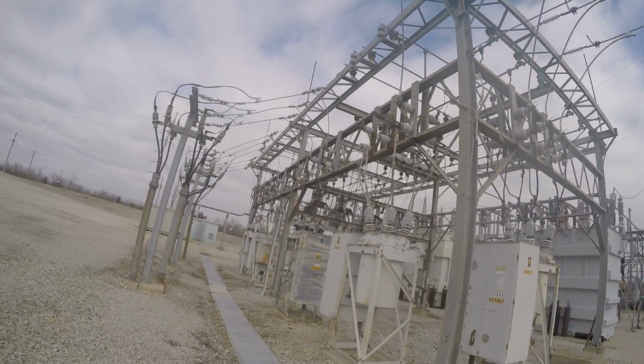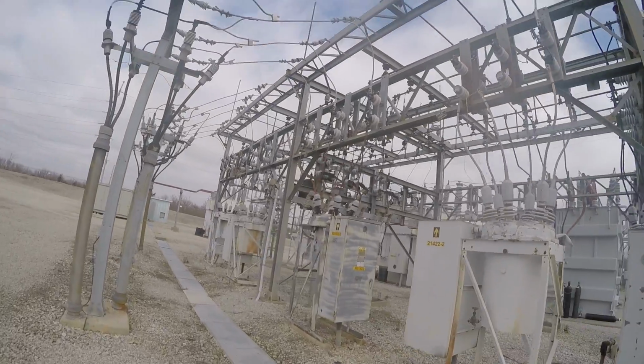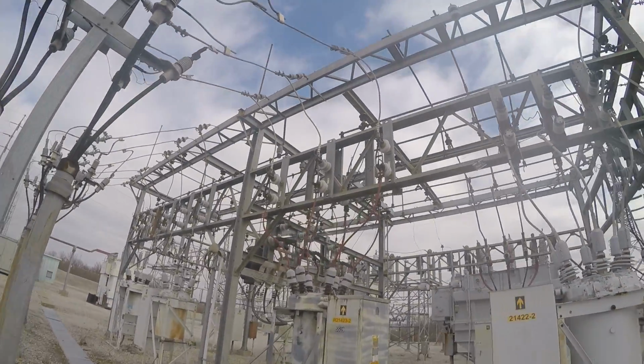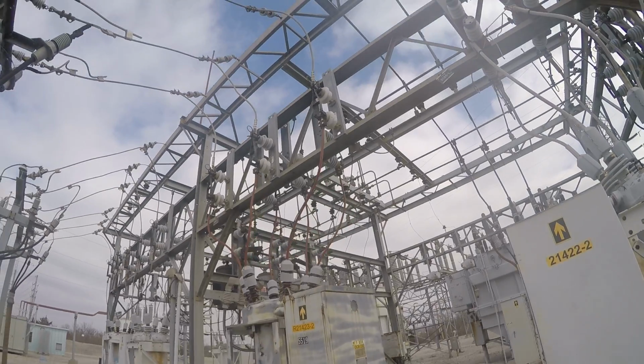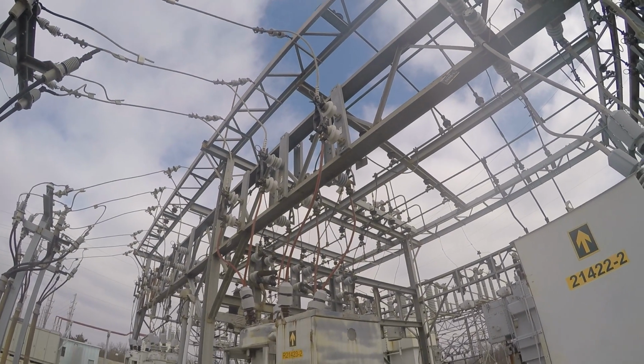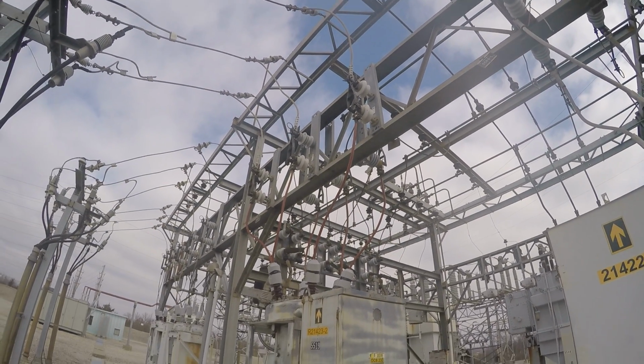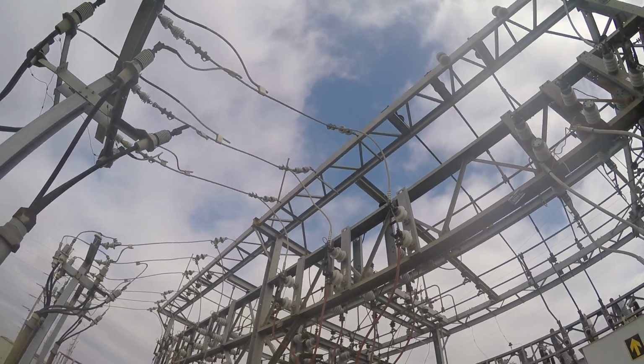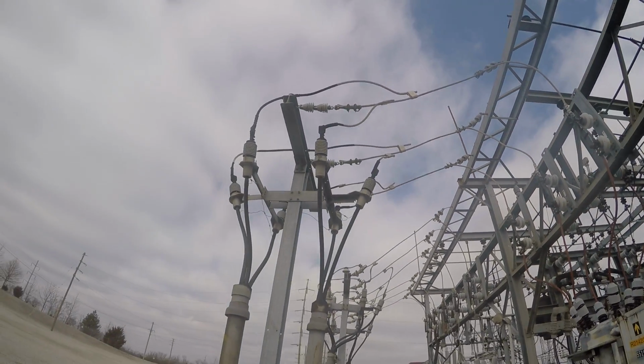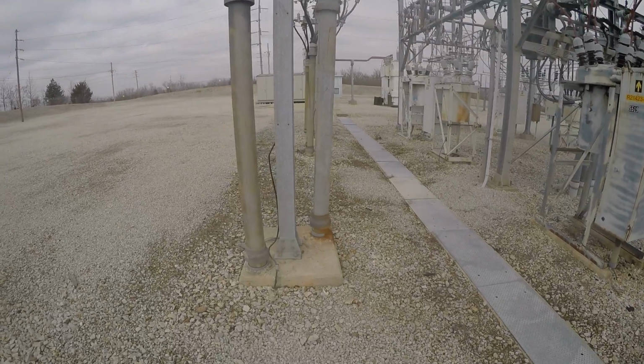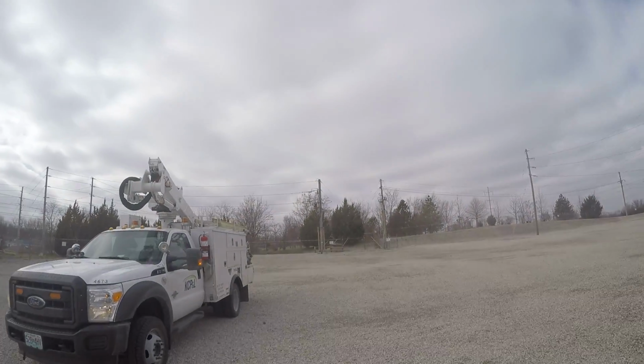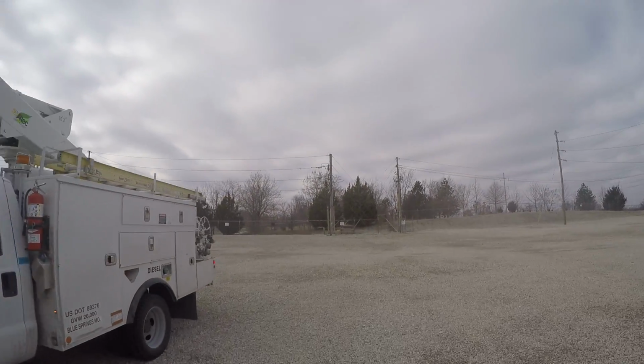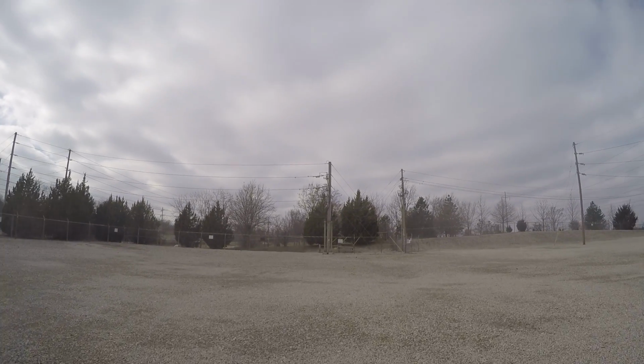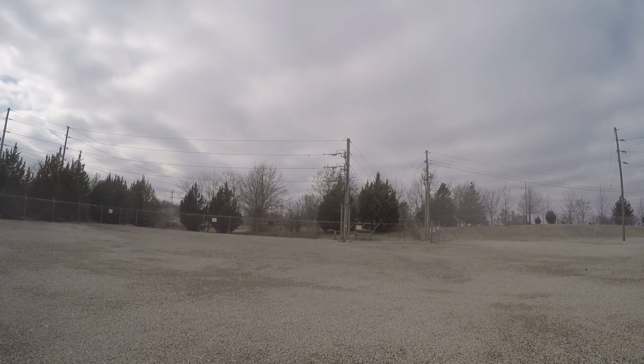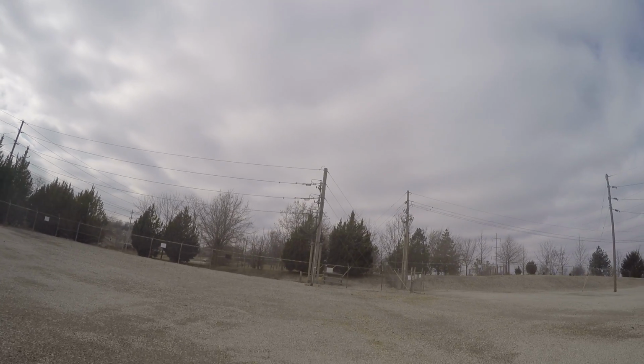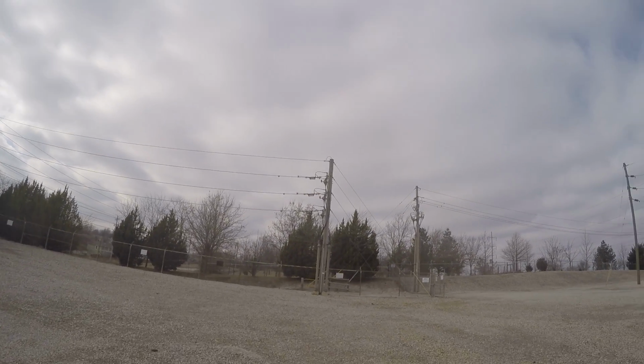Now, come over here to 21423. Same way on the inside. On the right, you have your source switches. Out here, the load switches, and then it goes overhead to a dip. This underground wire goes across the sub and comes up right over here to our terminal pole. 2 runs of 750 come up the terminal pole.